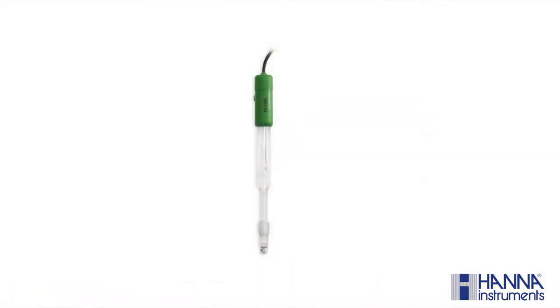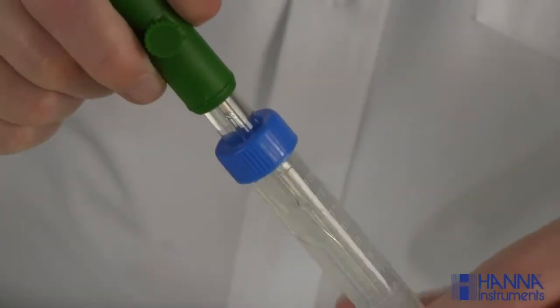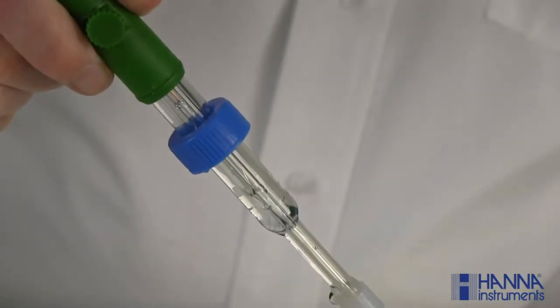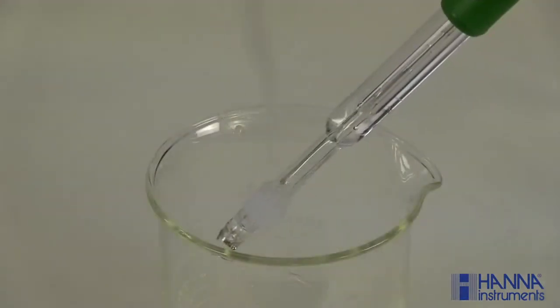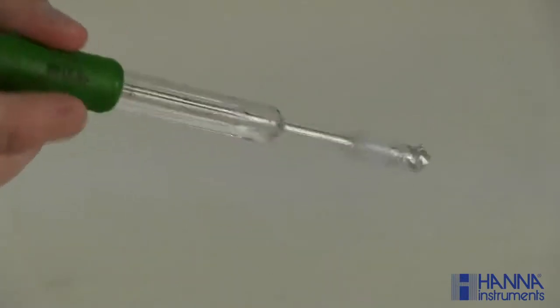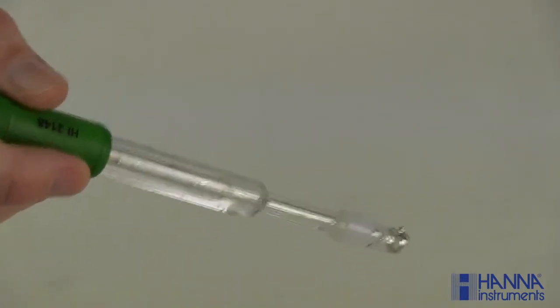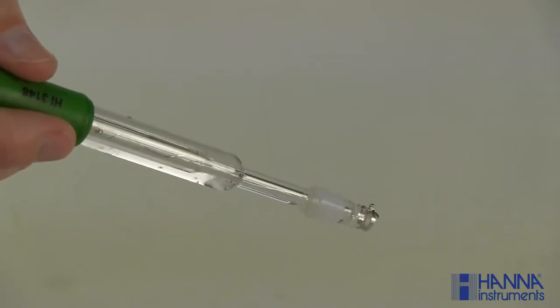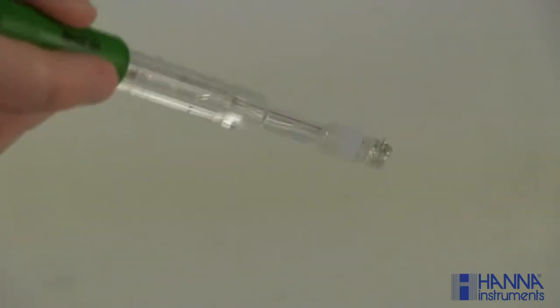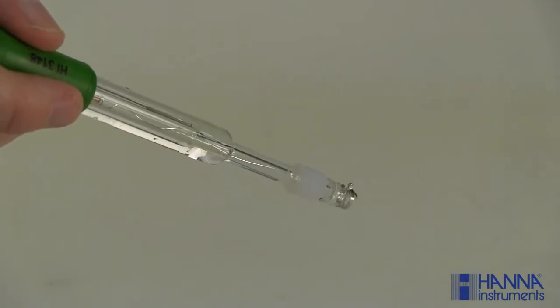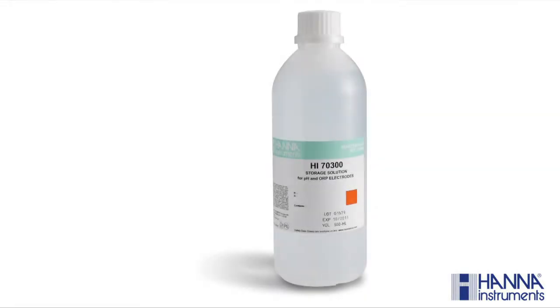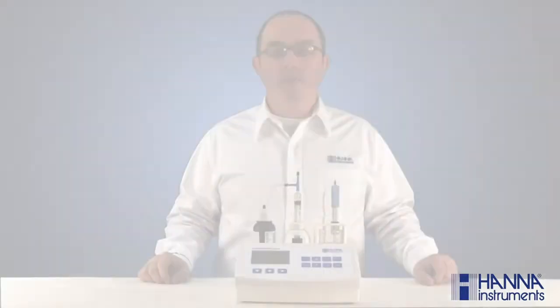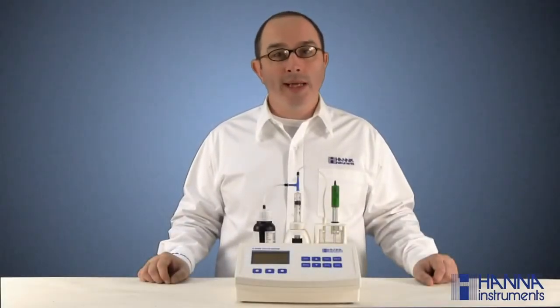The HI84500 mini titrator comes with the HI3148 ORP electrode. Simply remove the protective cap. Don't be alarmed if you see any salt deposits. This is normal. Simply rinse the electrode with DI water. Inspect the bulb for any air bubbles formed during transport. The electrode will not function properly if they're present. To remove these bubbles, simply shake down the electrode, as you would do with a glass thermometer. If the bulb is dry, soak the electrode in our HI70300 storage solution for at least 1 hour, and then connect it to the titrator. And that's it. Now we're ready to install and calibrate our dosing pump.